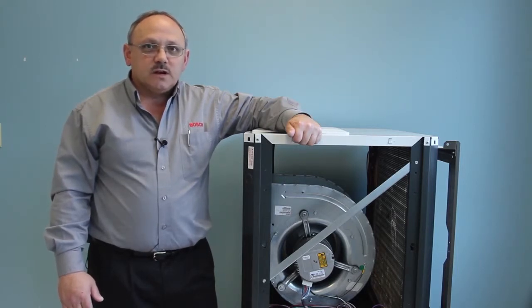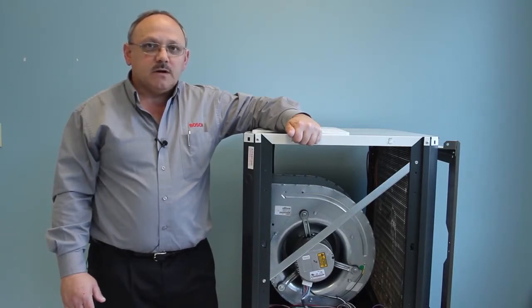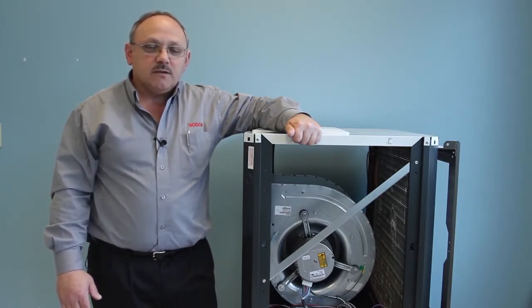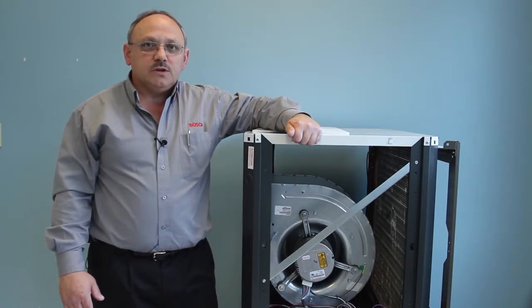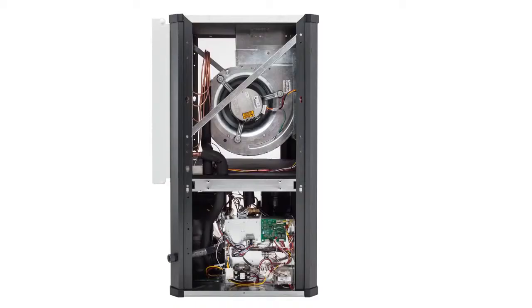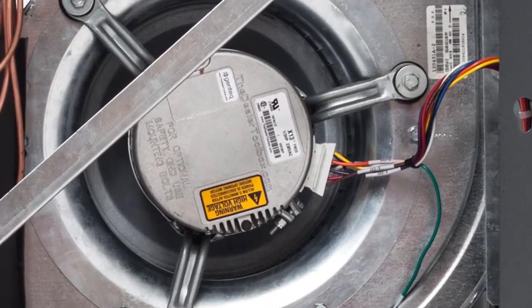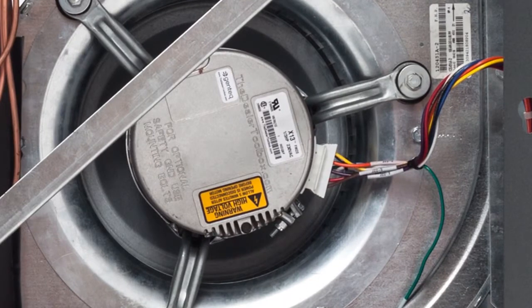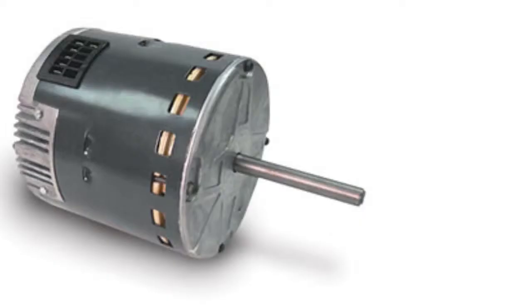Next, we'll cover the setup of the CTM or the standard motor, and then we will talk about the setup of the variable speed motor, which is a factory installed option, which is included on this SM model. After that, we'll go through the setup procedures for the UPM board. The constant torque or CTM motor is the standard blower motor on the new GreenSource SM model. The CTM is similar to the variable speed motor in that it is a brushless DC motor, it has a permanent magnet rotor, and it has the same efficiency as the variable speed motor.